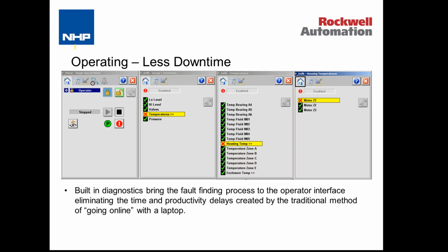Here's another example of this. So if we start with the faceplate on the left, we've got a faceplate for a motor, and it shows us here this red symbol here with the eye in it. That shows us there's an interlock trip on that motor preventing us from running. If we click on that red symbol there, it launches this next faceplate, and this next faceplate shows us that the reason the interlock is tripped is because we've got this temperatures input is not satisfied. If we click on the temperatures input, it takes us to the next faceplate, and it shows us here that it's this housing temperature that's tripped. If we click on the housing temperature, it then takes us directly to this faceplate here and shows us that it's actually motor Z1 temperature that is tripped. So we haven't had to go to the code, we haven't had to refer to any manuals, we've just been able to do all of that from the screen and identify exactly what has prevented us from running that motor.